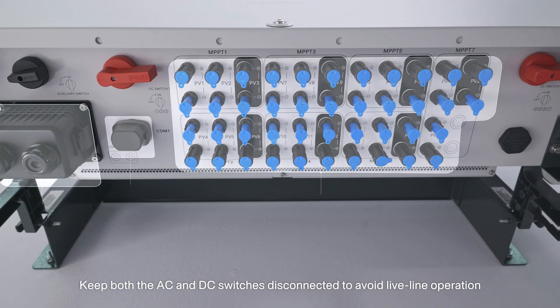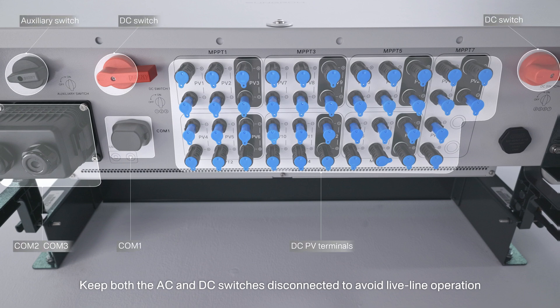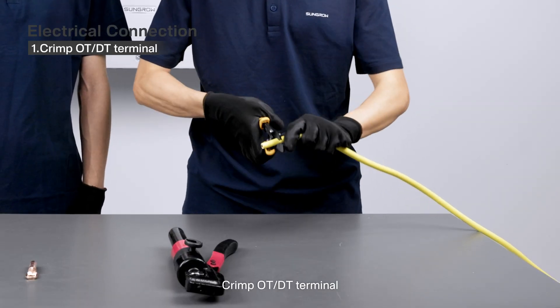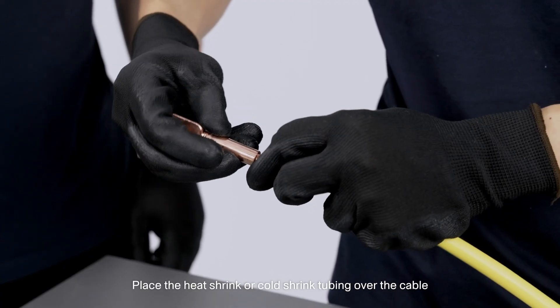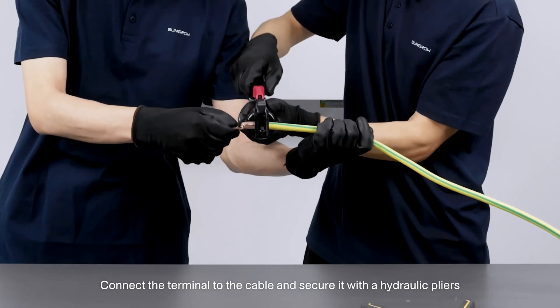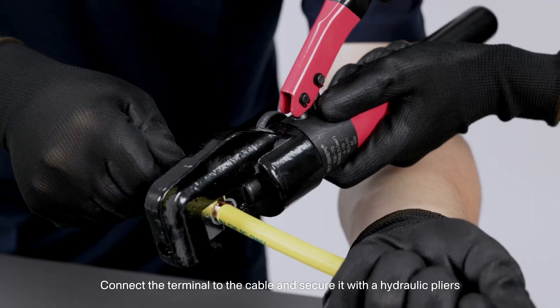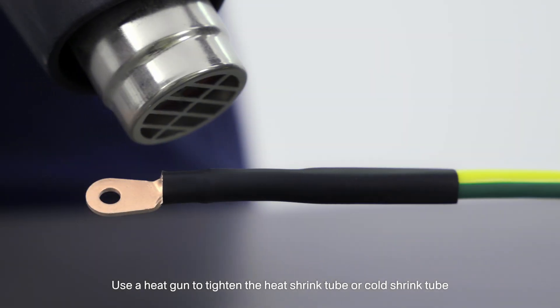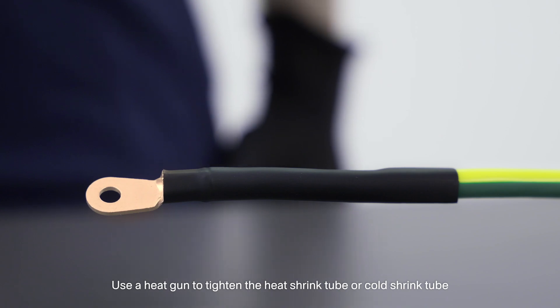Keep both the AC and DC switches disconnected to avoid live line operation. 1. Crimp OT or DT terminal. Place the heat shrink or cold shrink tubing over the cable. Connect the terminal to the cable and secure it with hydraulic pliers.